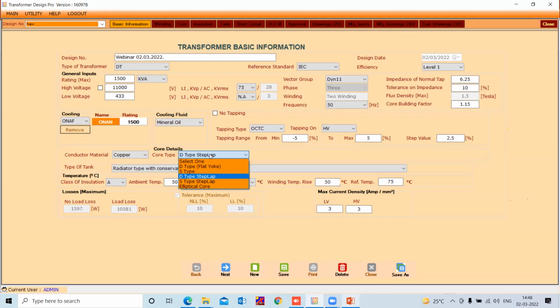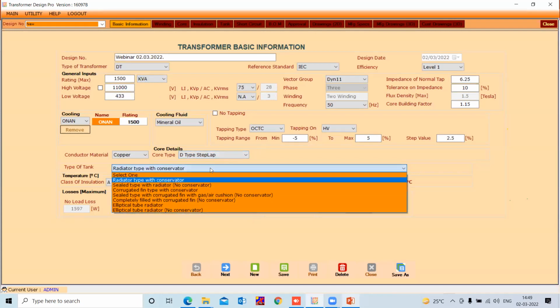Okay, we are on to the conductor material. Let's go for core type. The core types are shown here as D type, S type, elliptical core. There are more core options also possible for some of the ratings. Let's choose some of the other ratings and see whether other options are also possible for the core. Okay, let's see. For this 500 kVA rating, you are in a position to see here D type flat yoke, S type, D type step lap, the S type step lap, the wound core, shell, wound core, the core type, and then you have amorphous in shell and core, both configurations. You have elliptical core, you have rectangular core. Also, you have EI kind of core construction possible. Choose any one. If you want to show the different rating as you had chosen earlier, you can go for the same, and let's verify that whatever you have chosen earlier is there.